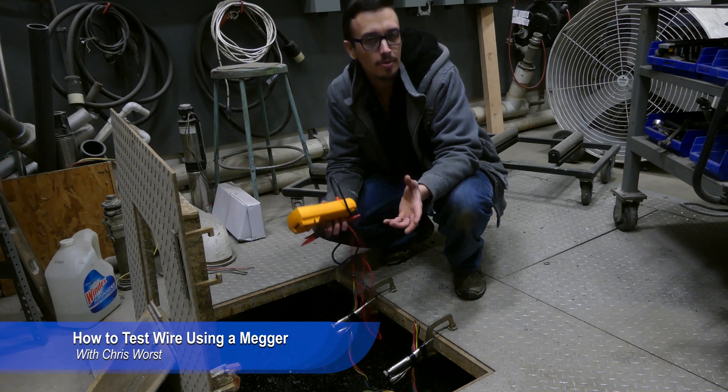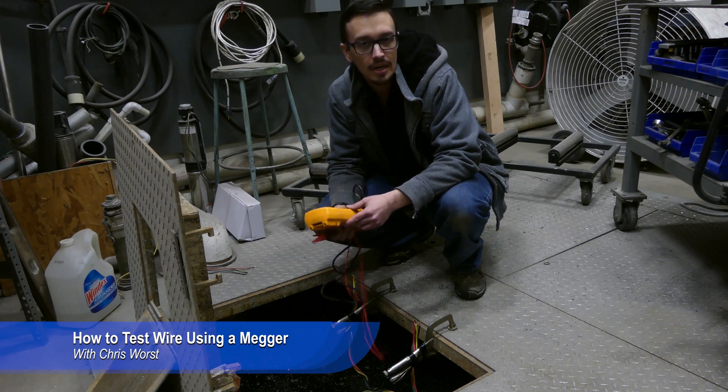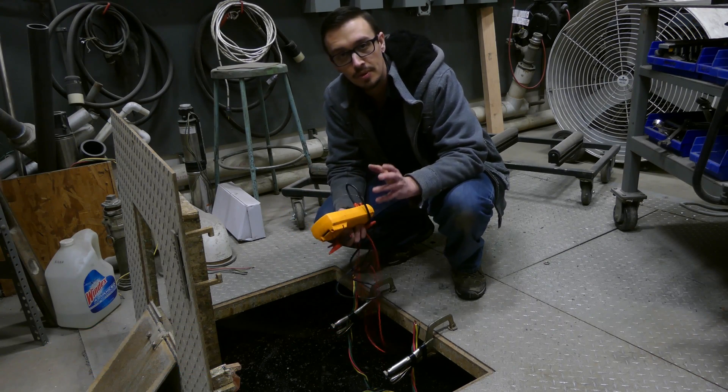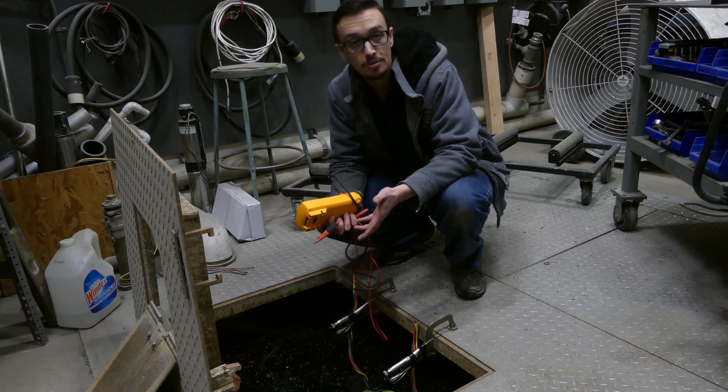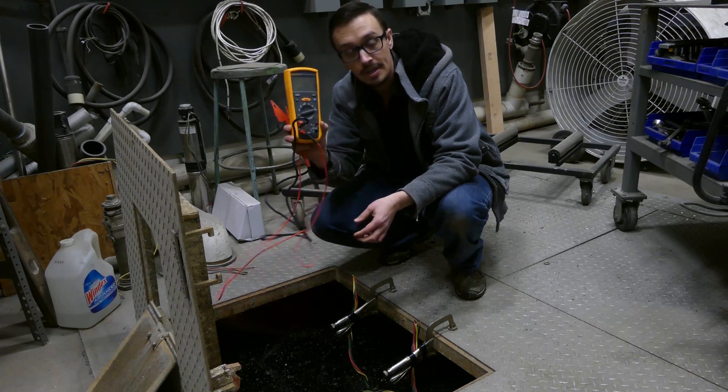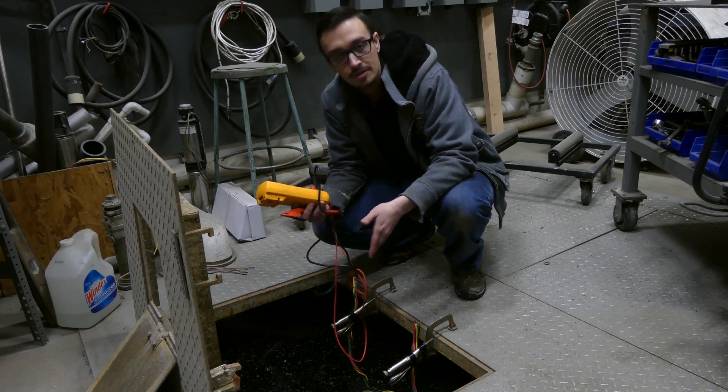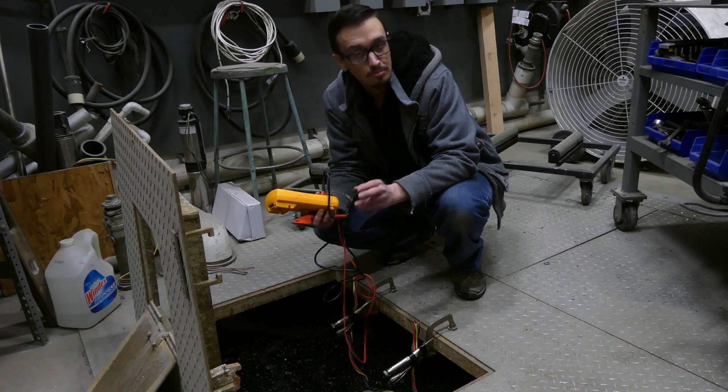This tip today is mostly oriented towards submersible well pump owners, but this could actually apply in any situation where you're dealing with cable that is submersed. And what we're going to try to show you today, we've got our megger again today, the second time we've used this in our videos. And what we're going to do is show you how to test the wire while it's submersed.